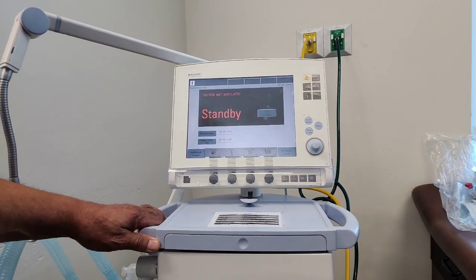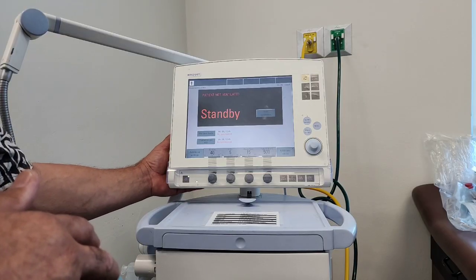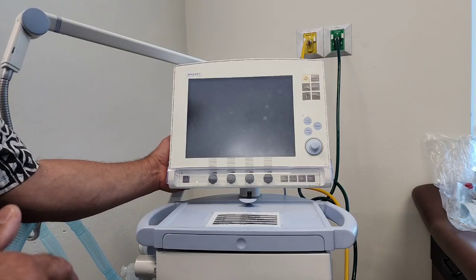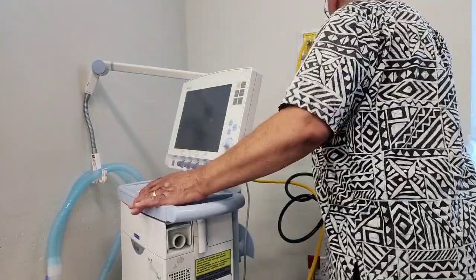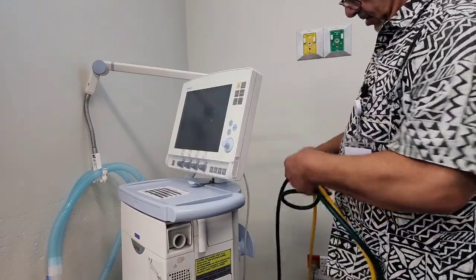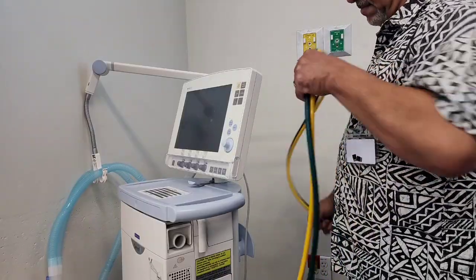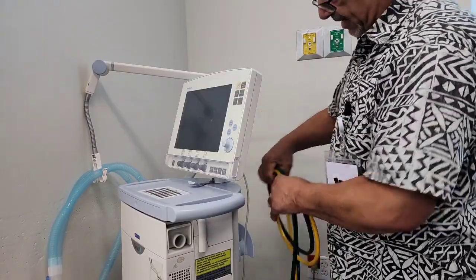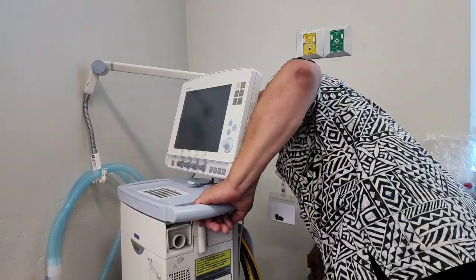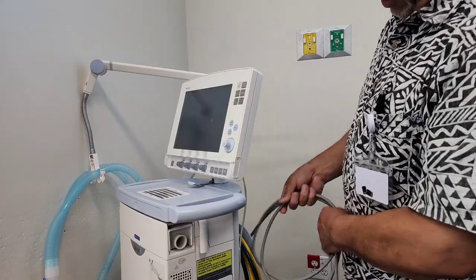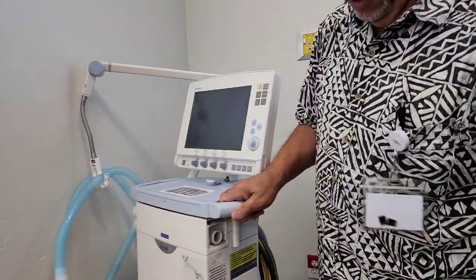So that's basically what you're going to do with your first lab on all 4 ventilators, okay? So now I'm done with this. I'm going to go ahead and shut it down, and I can go to the back and turn that little button off. Okay, then I'm going to disconnect the gas source. Remember, always disconnect the gas source when you are done on these ventilators. We here at Pima, we have oxygen piped in from H tanks down in the dental lab, and if you keep the gas plugged in, it will be used. The ventilator's constantly pulling gas from the wall, and it will deplete the oxygen.